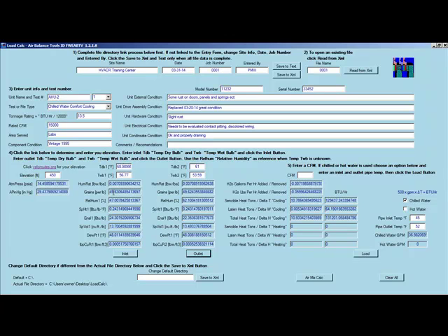And we got 49.63, 49.62. If I went to a 6, I would be over, so we're going to go 5.9. We're going to say 15,000 CFM.